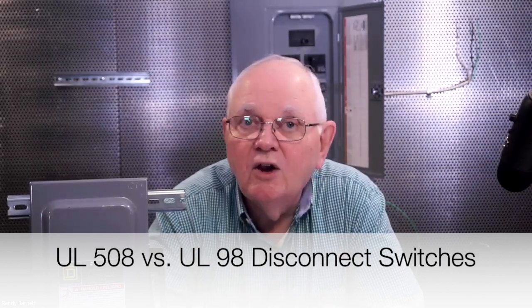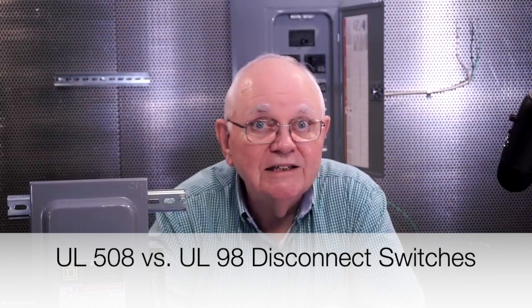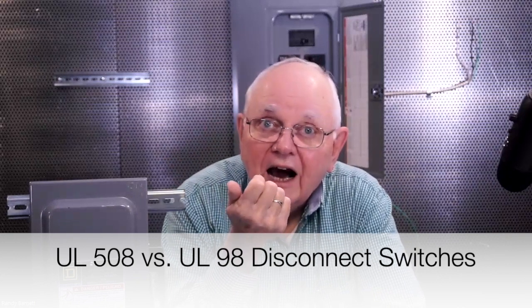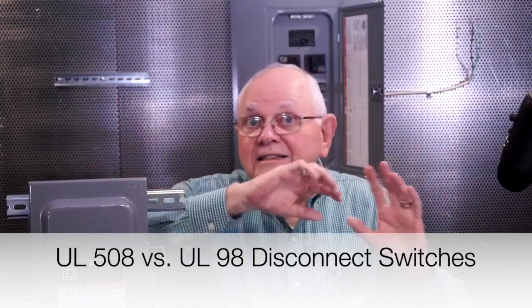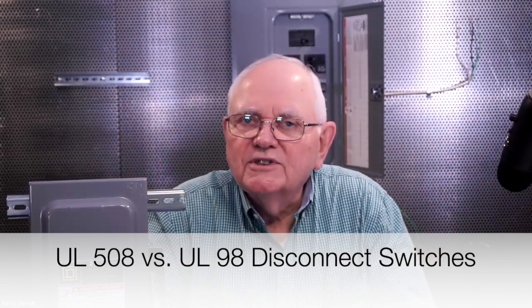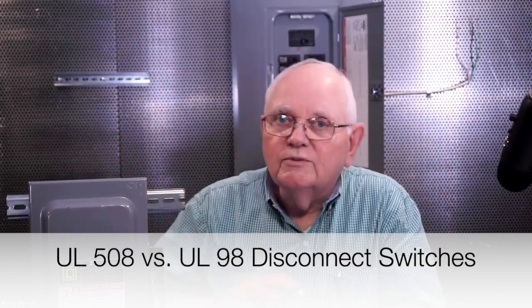So for instance, with the UL 98 disconnect safety switch, when I operate that one back at the big control panel, I de-energize everything. That's what it's given me for branch circuit protection. Now down closer to the motor, maybe I want another switch that's marked as suitable for use as a motor controller, because I could use it to start and stop a motor if I needed to. That's evaluated according to the UL 508 standard. So, a very brief explanation, but you'll hear the terms UL 98 and UL 508 switches if you work with industrial machinery and automation systems. You've got to make sure you have the right one in the right location, right?